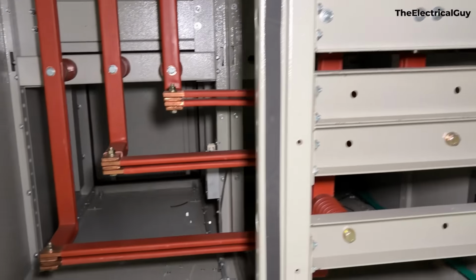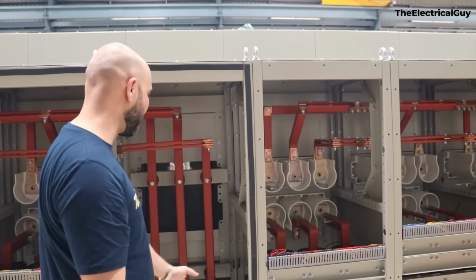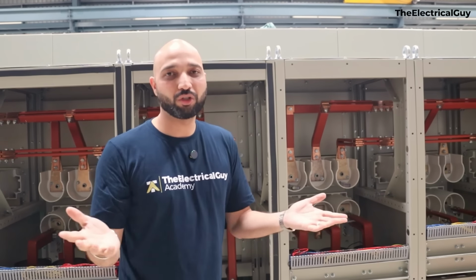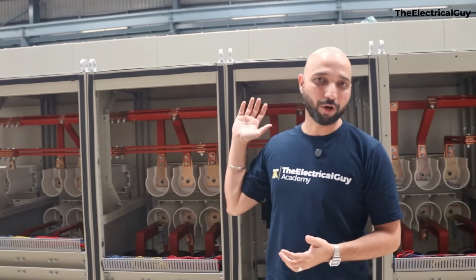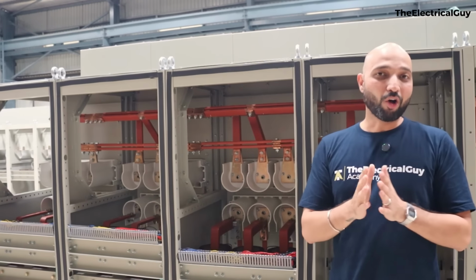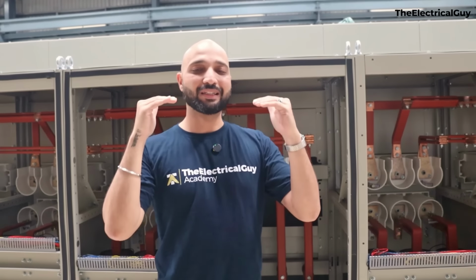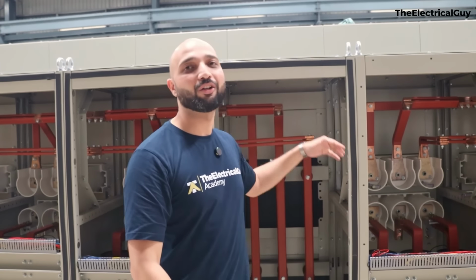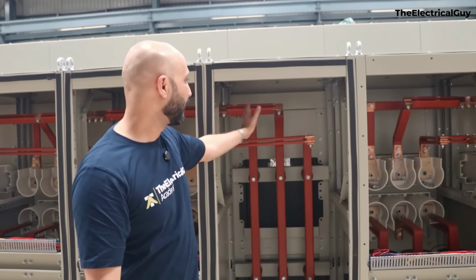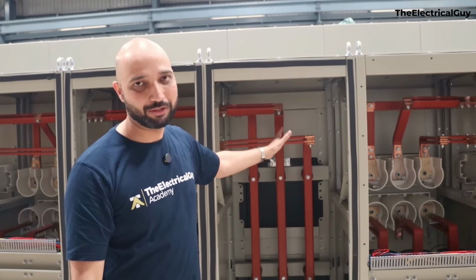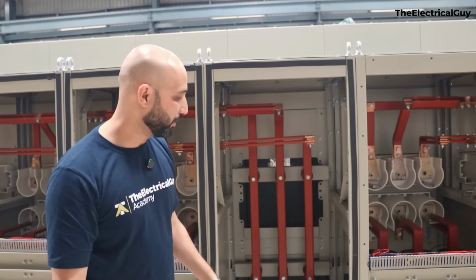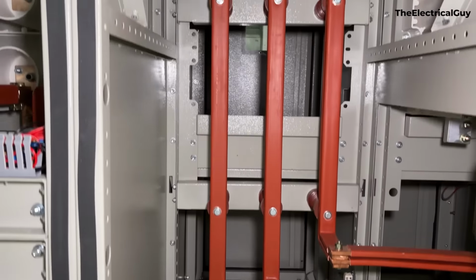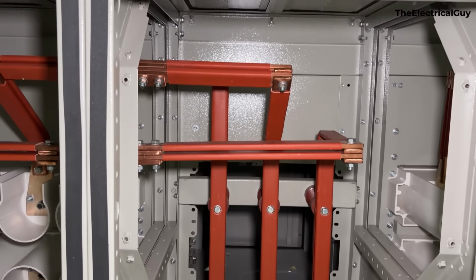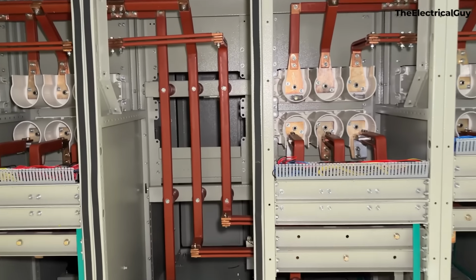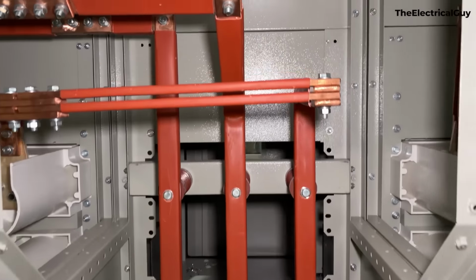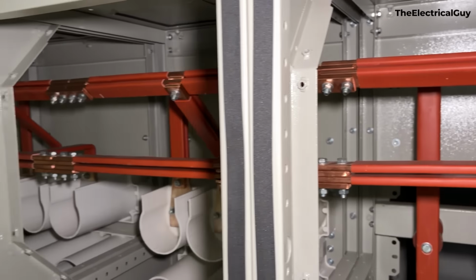Now, if you want to connect the incomer panel, you'll have to run the bus bar at the bottom and then connect, which is not ideal because our bus bars are running from the top, right? So in order to put these two bus bar in the same level, we need to raise the height of the bus bar so that we can connect the incomer 2 to our main bus bar, right? And that is what we are doing. You can see the bus bars here. It's coming horizontally at the bottom, and then we have connected the bus bars here, and we are just raising the height of the bus bar. And that's the reason why we call it as the bus riser panel.